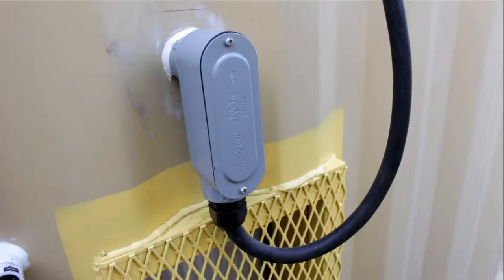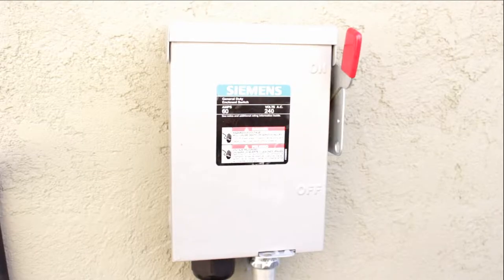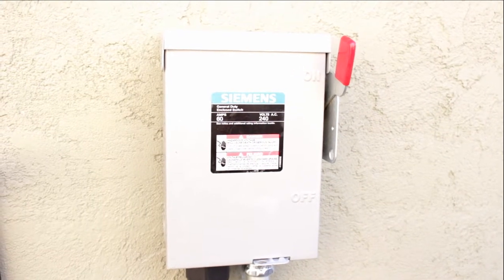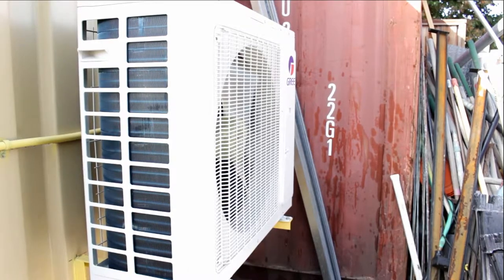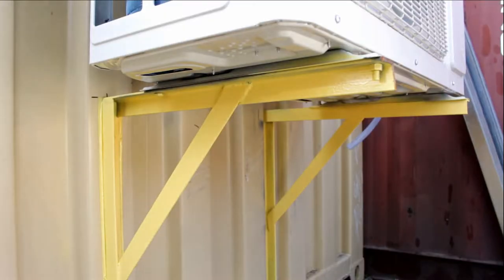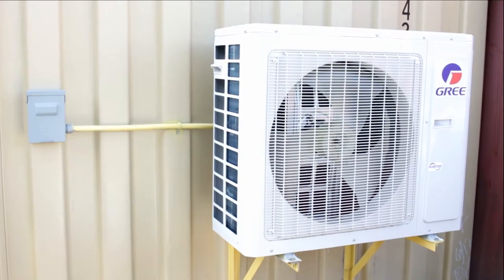The Box comes with 20 feet of 6/4, 600-volt UL-rated portable cord, ready to be installed to a 60-amp disconnect or your electrical panel. It also comes with a 3-ton Gree ductless split unit mounted on the backside of the container for easy transportation, and a 30-amp disconnect for easy service.